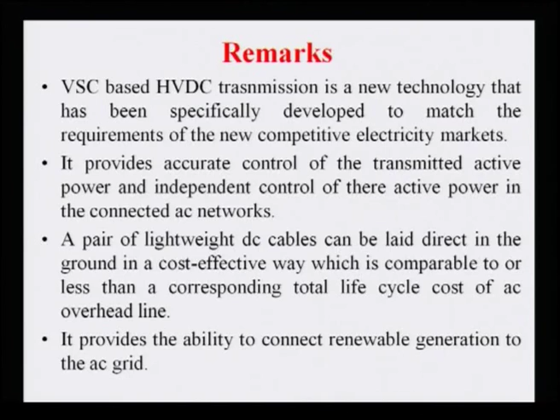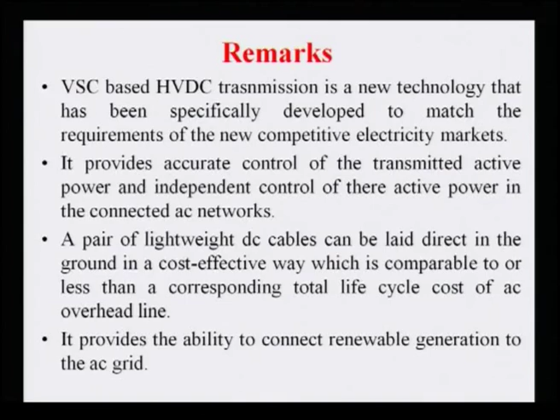That is why DC cables are more preferred, especially if you have submarine cables, or cables in the sea, or you are going for longer distances. A DC cable can carry up to 50% more power than the equivalent AC cable, because of the charging effect. So, it can load more, and that is why it is more stable as well. So, there is no need to install groups of cables to achieve the required rating. There is no need to go for several cables to achieve the same rating, since it is already 50% higher than your AC cables.